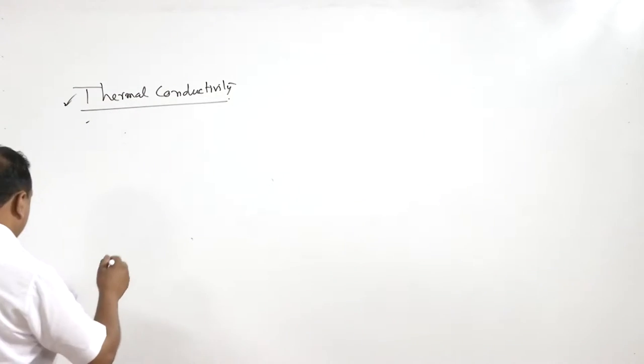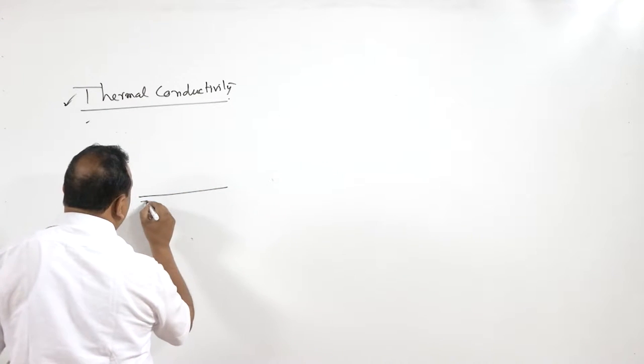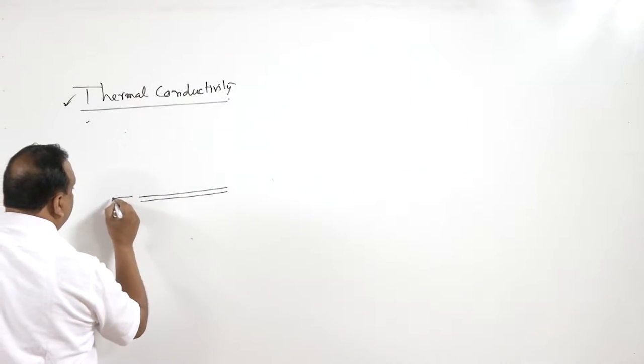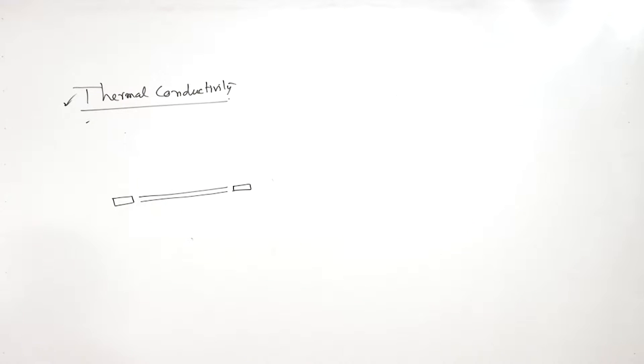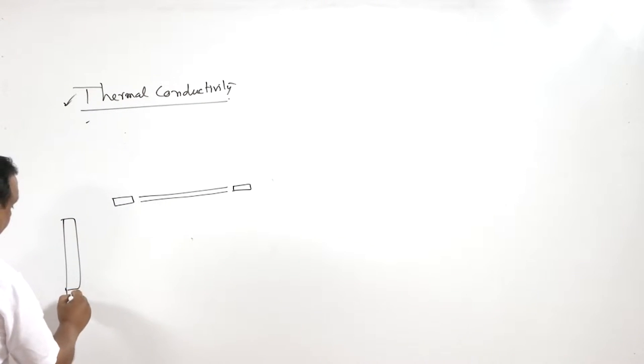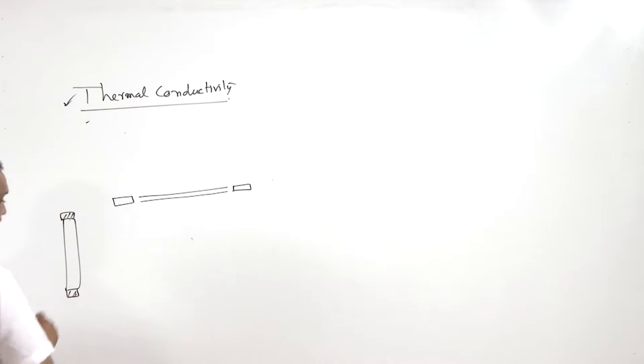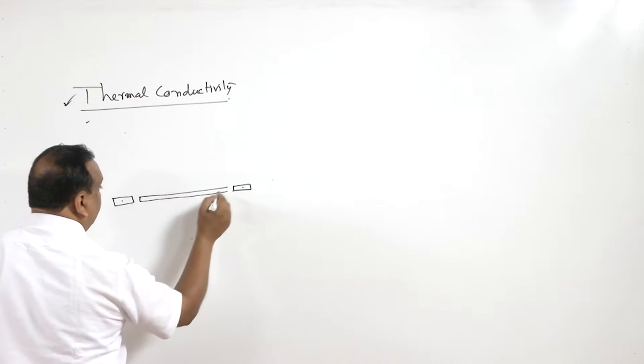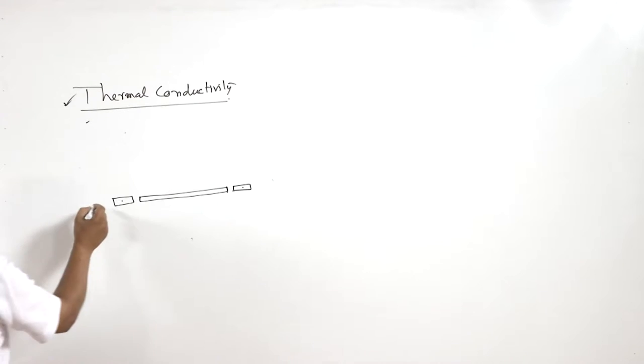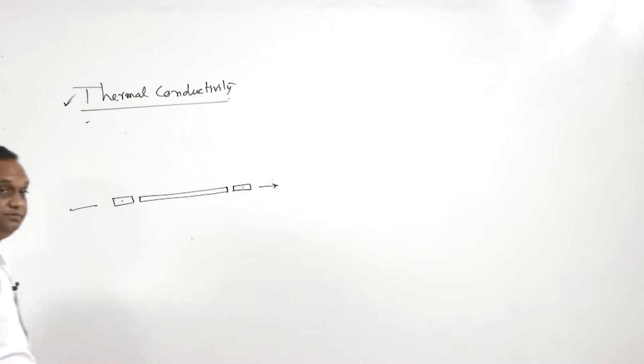In this system there is a thin plate with guard heaters on both sides. Even if the bare plate were insulated, a temperature field would still develop — especially if the material is itself insulating. Guard heaters are used to prevent this; their temperature is matched to that of the plate, so there is no heat transmission in the lateral directions.